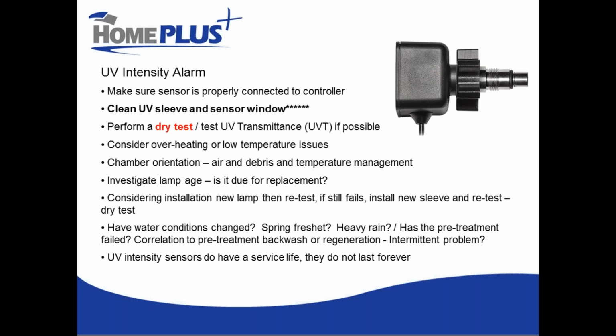And lastly, UV intensity sensors also don't last forever. They do have a life and they can fail. So particularly if you have tried a new lamp, a new sleeve, you've done dry tests, and it's definitely seeming to be equipment related, the next thing to try would typically be replacing the sensor itself. And if you're at 7 or 8 or 9, 10 years on a sensor, that's a pretty decent chance that that sensor is just at the end of its life. They're designed to fail by being less sensitive than a new sensor would be, so they always fail in the safe direction.